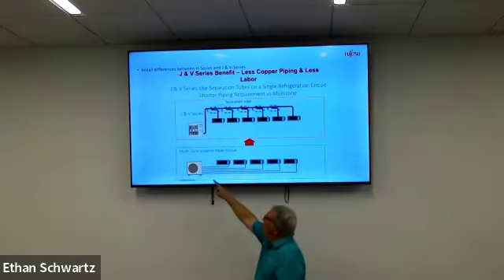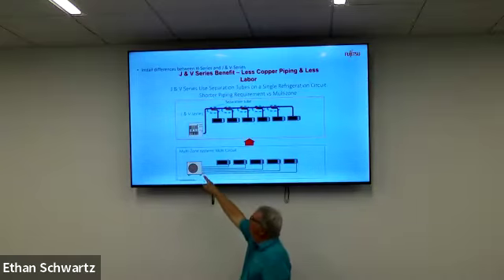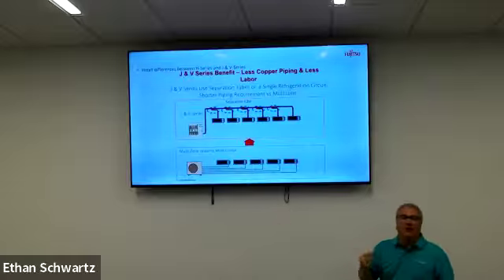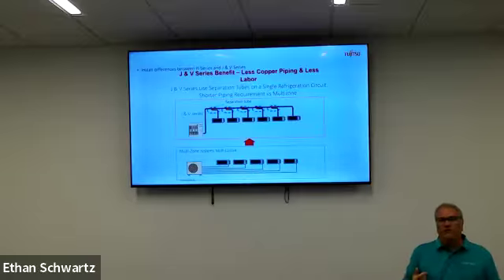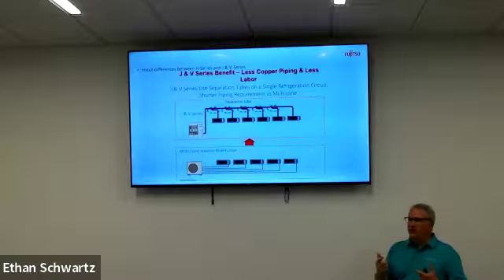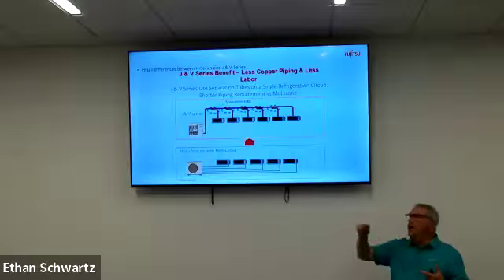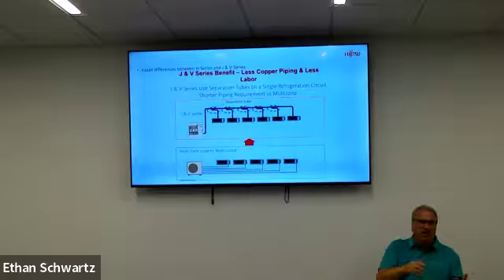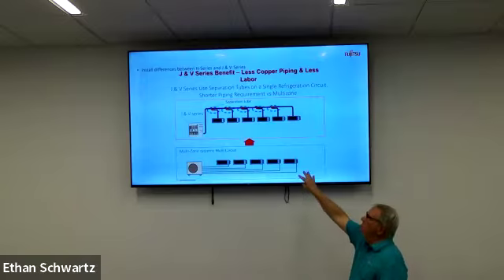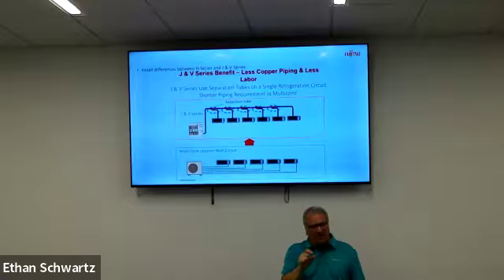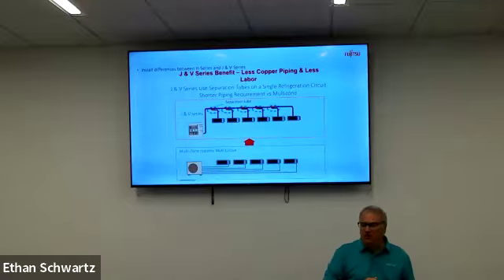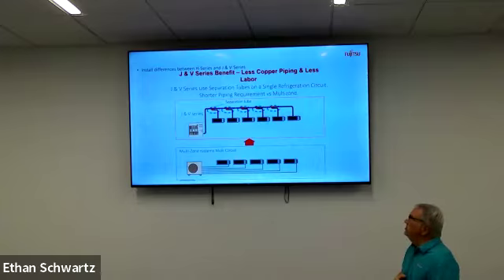So because of having electronic expansion valves here, you have limited line set lengths. And I'm sure you've seen in our tables and other manufacturers' tables, we have to have this aggregate total. No one of these zones can be longer than this. It can't be shorter than this number. And there aren't the same types of limitations, as many limitations. There are some limitations with the J series product and also the V if doing a smaller job.